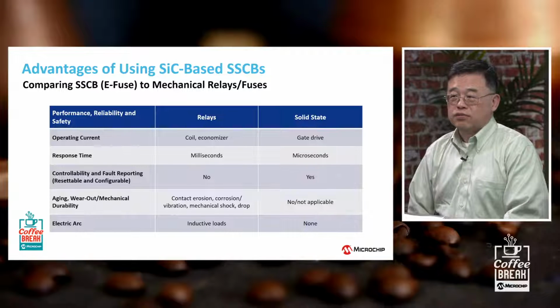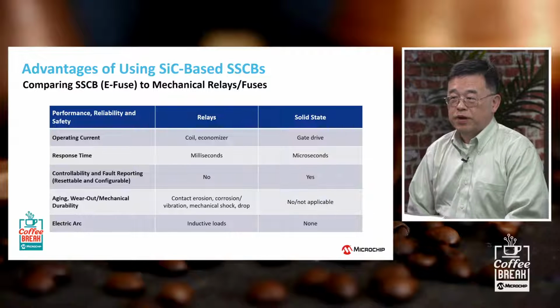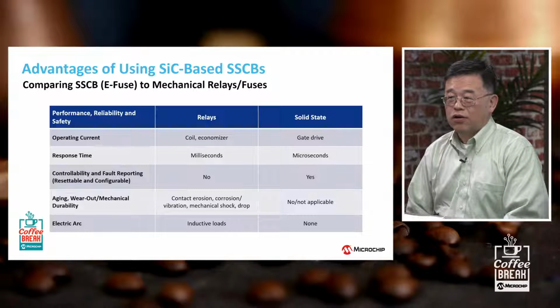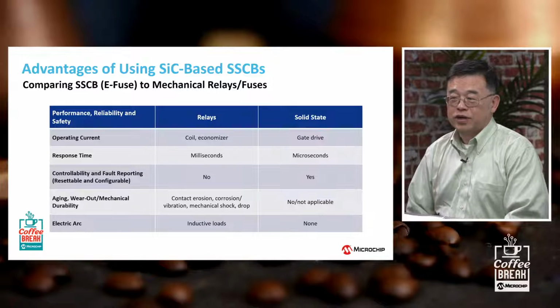The other one is the response time. It's very fast. A traditional relay might accumulate energy to a certain point, detect a fault, and trip. At that time, when it switches, there could potentially be an arc, and that arc could be a spark that's not good if you're in a fume or hostile, explosive environment, and it could be damaging equipment.